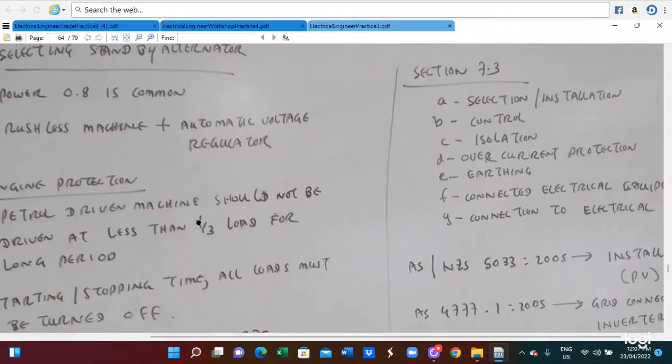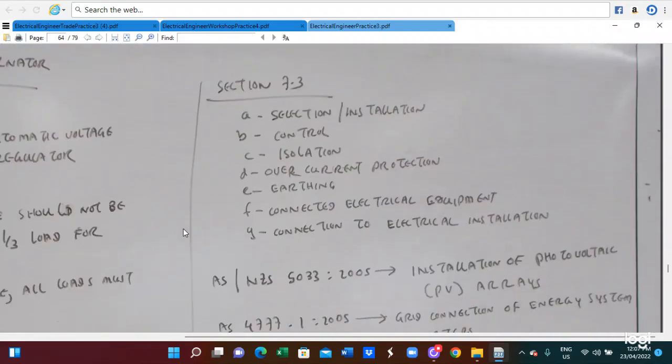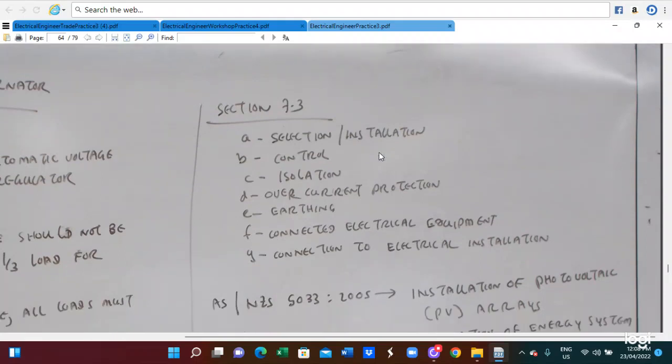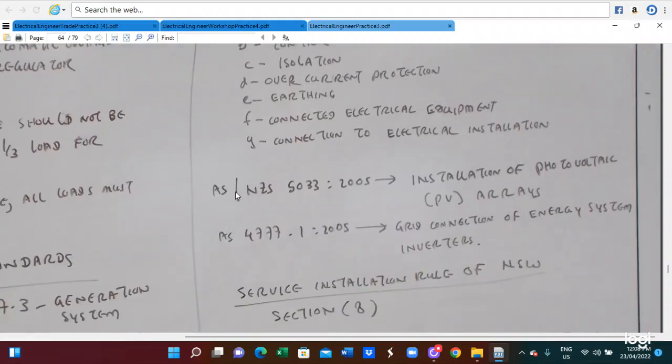So this is section 7.3. In this case, A is selection and installation, B is control, C is isolation, D is overcurrent protection, E is earthing, F is connected electrical equipment, G is connection to the electrical installation. This is for section 7.3 of AS3000. It mentions the installation of the emergency alternator system.